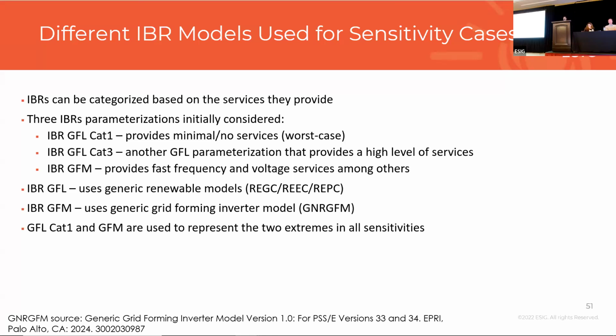They can provide the fast response that we've been asking for. Something like what Ireland asks for, 150 milliseconds of fast frequency response, this resource can provide. FinGrid asks for extremely fast voltage control at a turbine level, this resource can provide it too. So that's the kind of resource we're looking at here, the bleeding edge of grid following, which can be stable in low short circuit systems and can provide a lot of services to the network. We're calling that category 3.